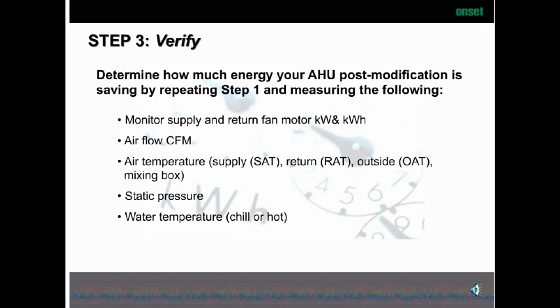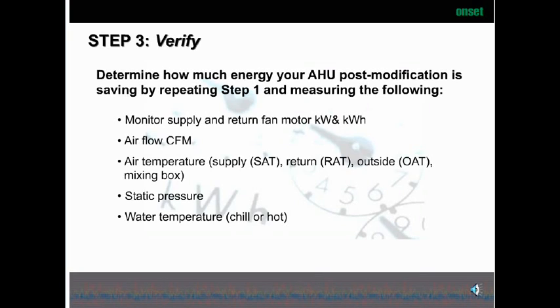After you've modified it, now it's time to verify. Did the modifications actually work? We're going to repeat the steps we did before — monitor the supply and return fan KW and KWH to see if any reduction has happened. Also the airflow in CFM, temperatures, static pressures, and water temperature. Taking this information, we can then determine whether the system is running more efficiently than it was previously.